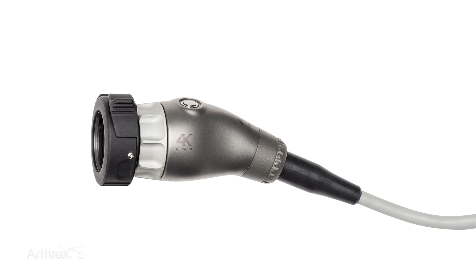Well, there's two significant challenges with autoclaving. Number one is heat, and steam is a great heat delivery mechanism. It creates a lot of energy and delivers it quickly to the devices that are within the sterilization chamber. And second, the penetration capability of steam is excellent, which is why it's such an effective sterilizer. But as well, it produces challenges for medical devices to withstand that penetrating capability and the heat shock. So both of those things have to be in close consideration for Arthrex when developing the camera head to survive autoclaving. And the challenges are fundamental to camera head design.